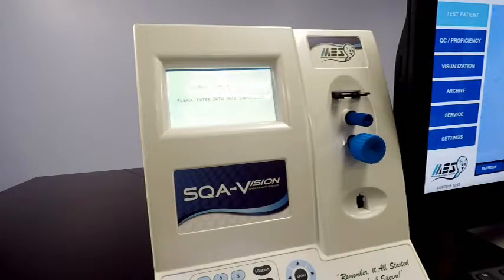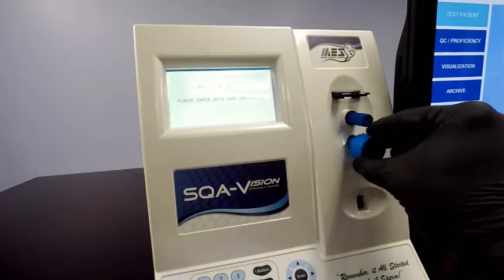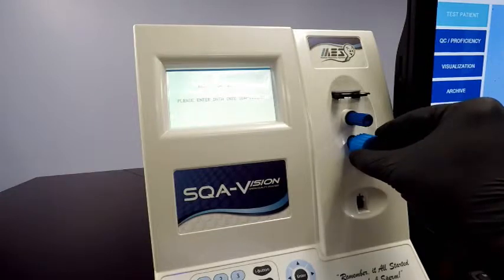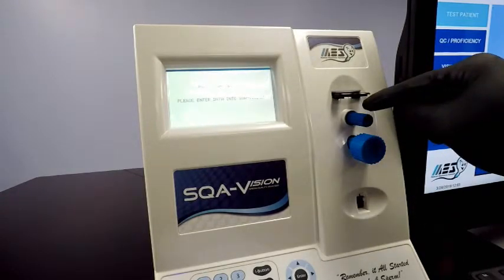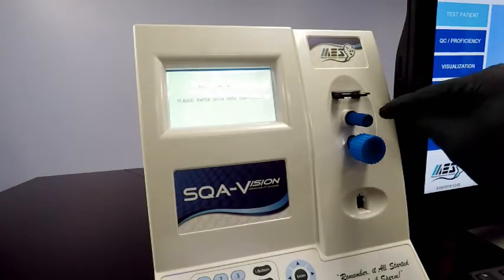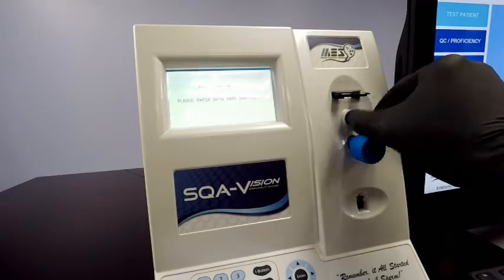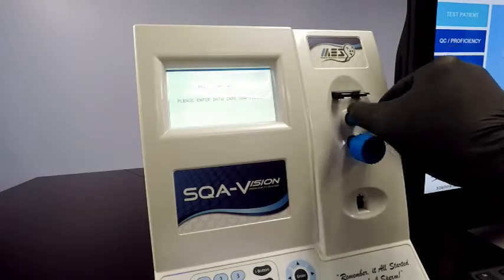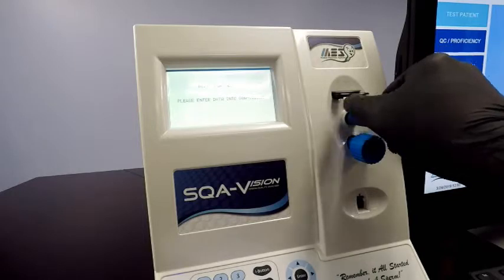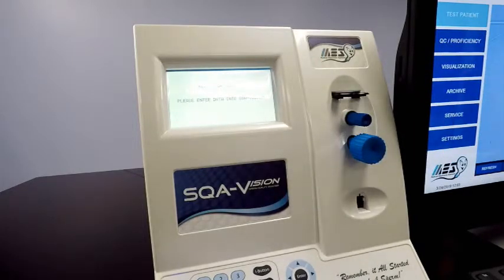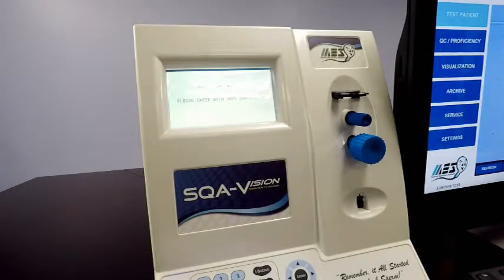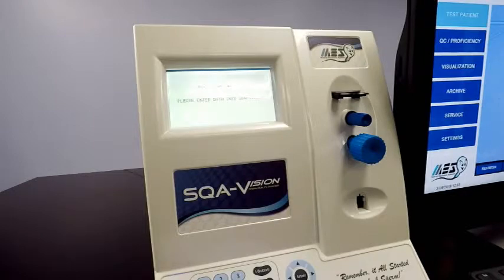Slide the slide adapter into the visualization chamber here. You notice there's two sides so you can load two samples at once if you want to scan through 100 fields instead of just 50. The first thing we're going to do is focus the sample. This larger knob here is going to focus in on the sample, and this knob here is our stage mover. What we're going to do is turn this either way all the way until it locks out on one side. Once we're locked out, now we can scan all the way through to the other lock point going the opposite direction. When we do that, we're going to get 50 fields of view.